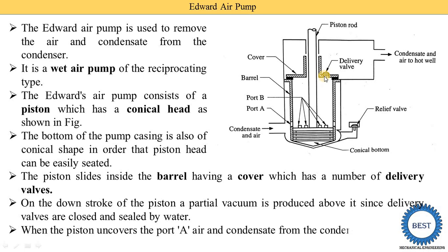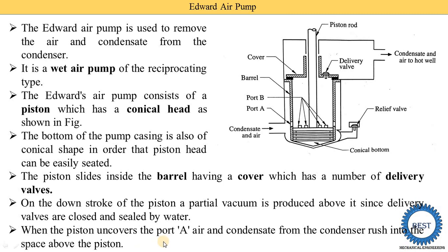When the piston uncovers port A — as the piston moves from the upward to downward stroke and reaches below port A, uncovering it — at that time, air and condensate from the condenser rush into the space above the piston. The condensate and air from the condenser enter the upper part above the piston.